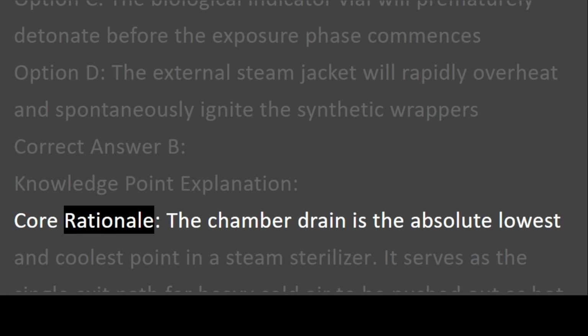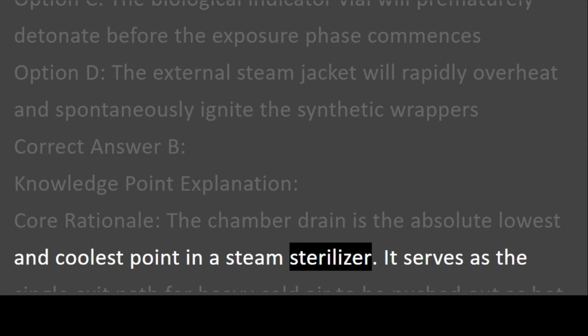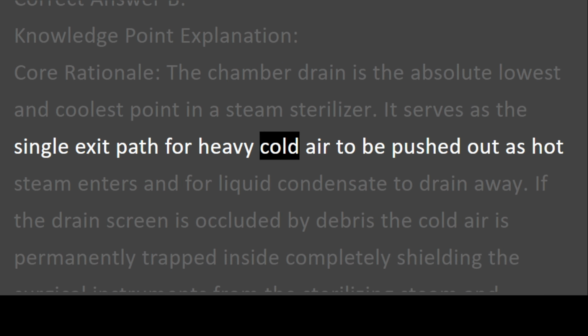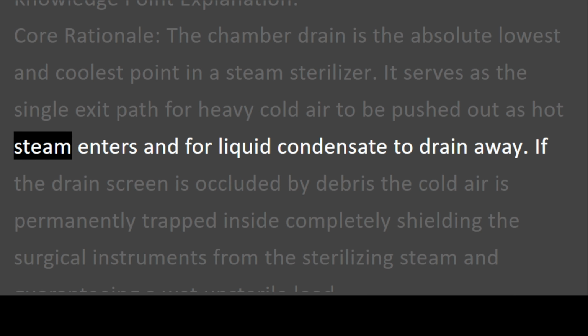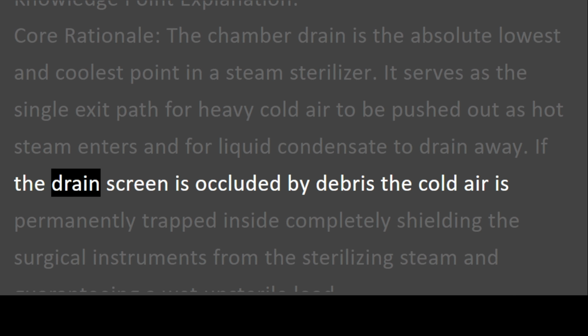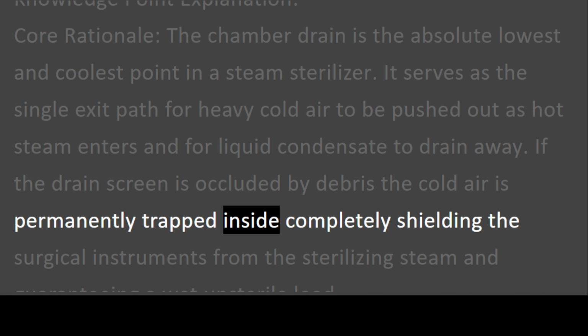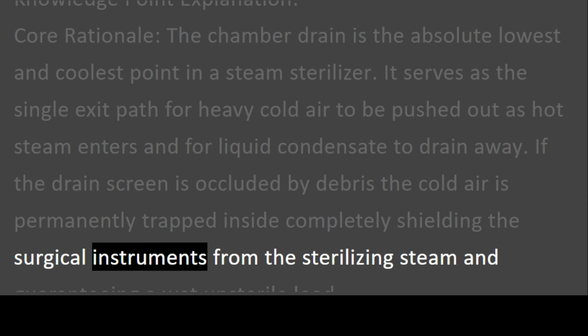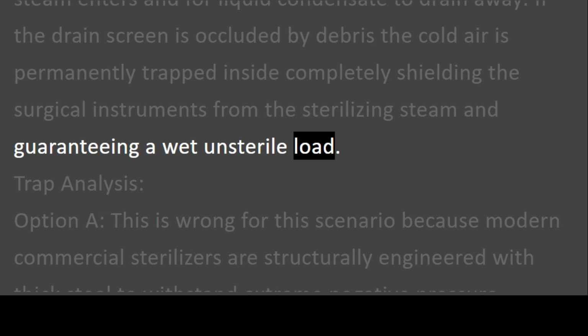Core rationale. The chamber drain is the absolute lowest and coolest point in a steam sterilizer. It serves as the single exit path for heavy cold air to be pushed out as hot steam enters and for liquid condensate to drain away. If the drain screen is occluded by debris, the cold air is permanently trapped inside, completely shielding the surgical instruments from the sterilizing steam and guaranteeing a wet, unsterile load.